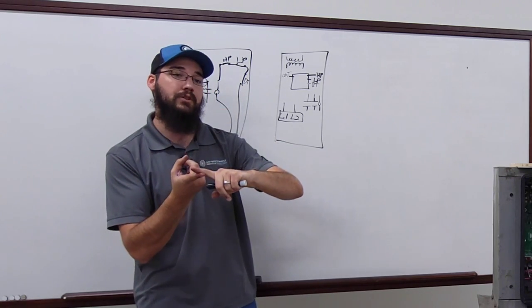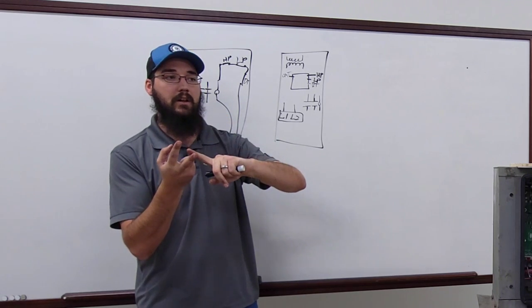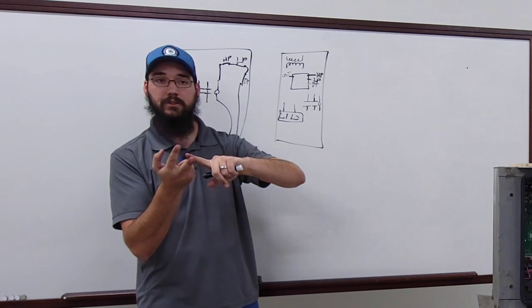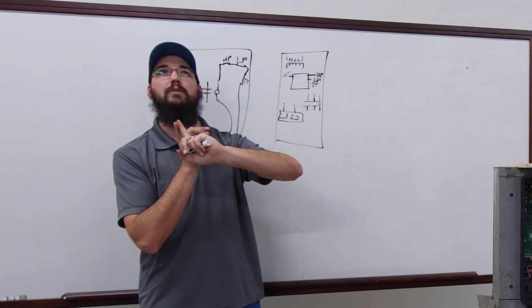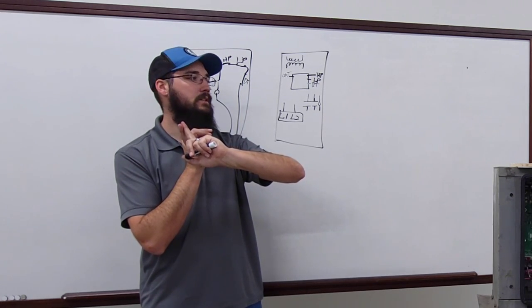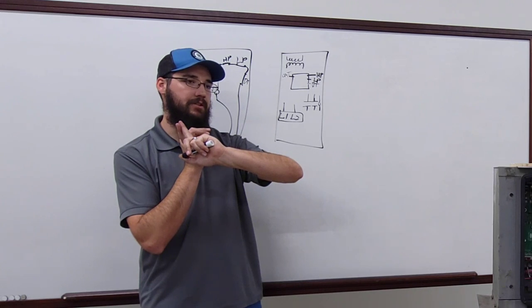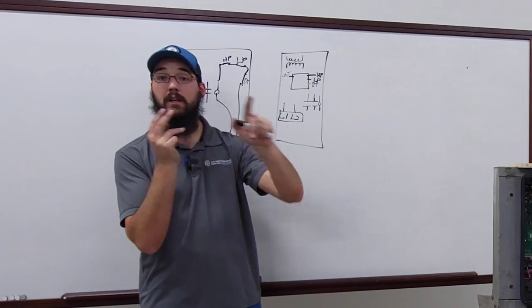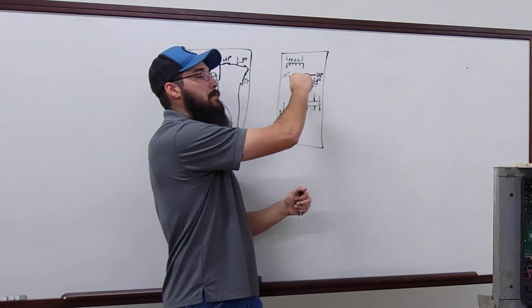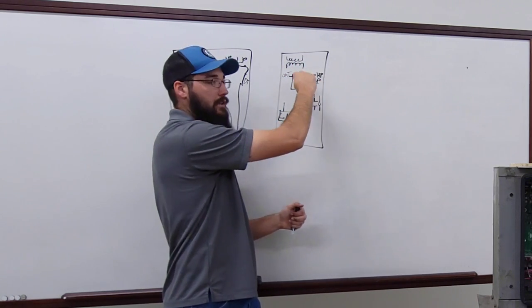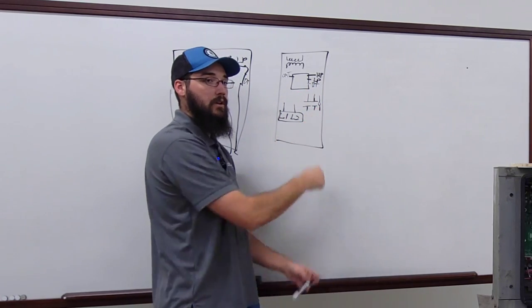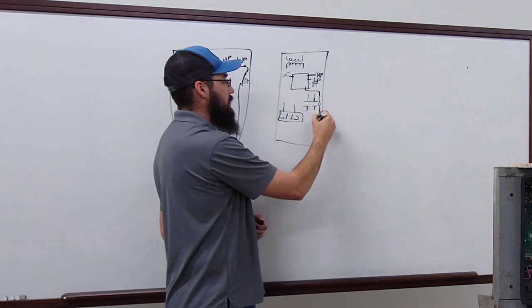That circuit failure could mean the compressor temperature overheated, it could mean a winding temperature — those have internal safeties on the windings — or it could mean a high pressure. You have multiple safeties ran. Those three sensors could still be ran in series on something like a split system, but the difference is it's not ran in series with the coil. This coil will have a separate output just to control it. Technically, a high pressure safety would be considered an input.